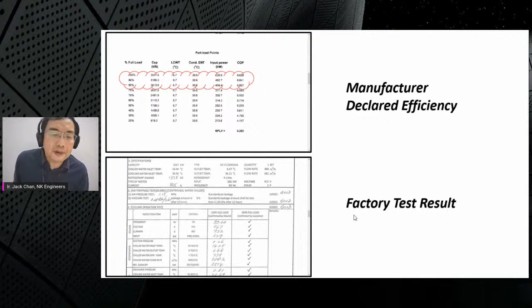There's no point in getting the most efficient chiller if you don't test it. The chiller itself may not be performing, even though it's declared efficient by the manufacturer. So you have to test it, and bring it to the factory to test. Once it has been tested, you operate the chiller, and we will have to do a site test. A site test is very important.